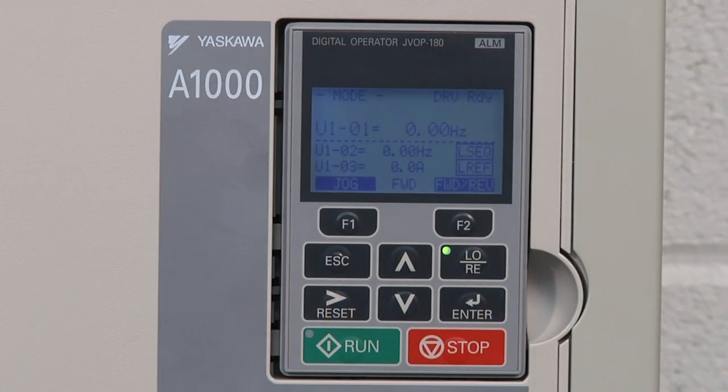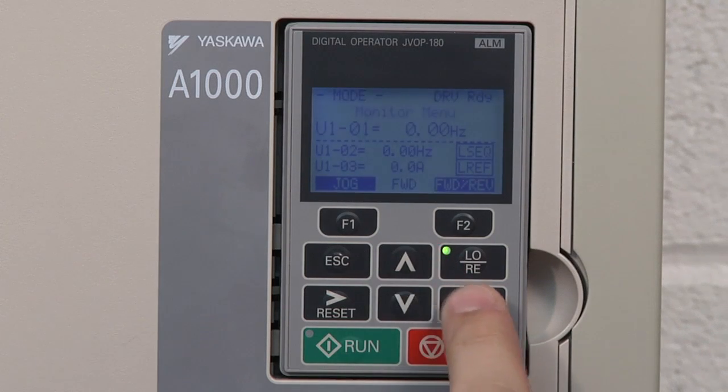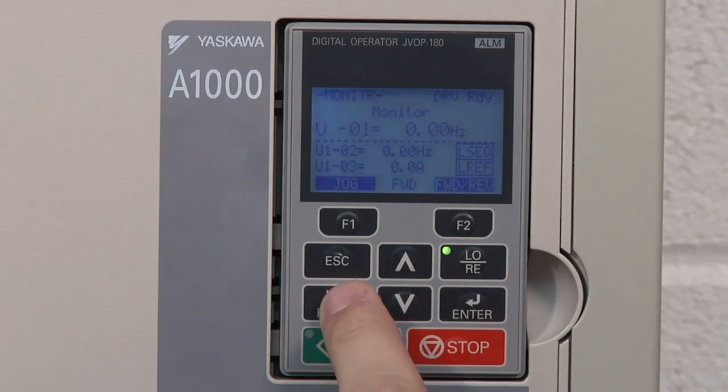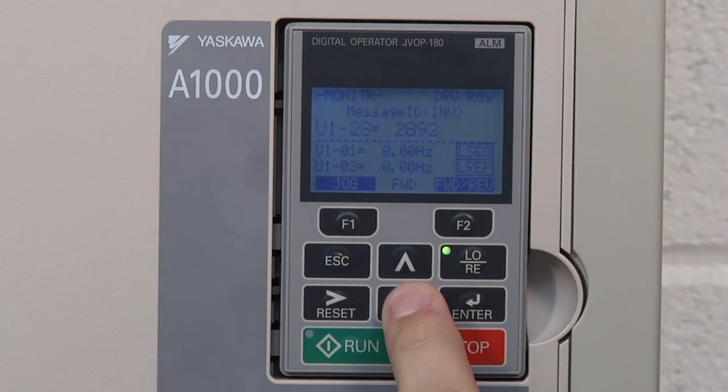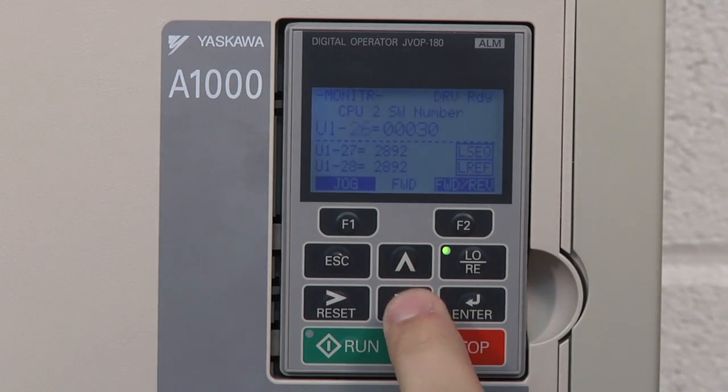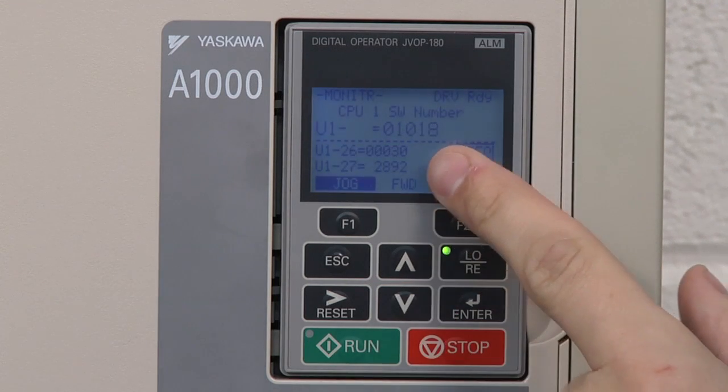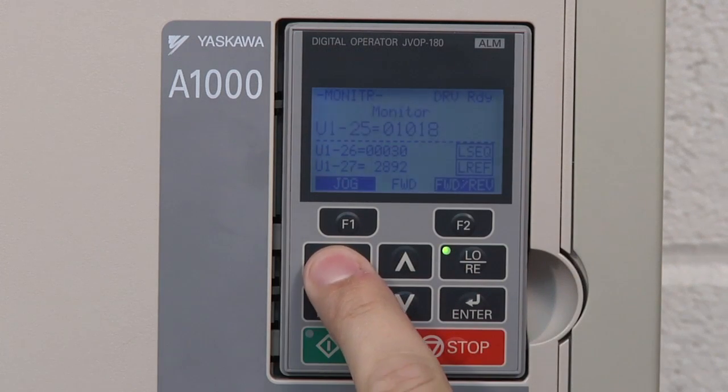Complete the flashing process by checking the drive's display. Access the keypad and move through the LCD display to the U1-25. If you see the latest version of the flash file in the display, congratulations, your system has been successfully flashed.